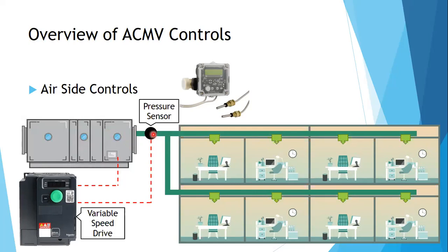So if this pressure sensor, for example, we put a set point of 10 Pascal, and this unit is running at 100%, this pressure sensor will read 10 Pascal. If one room closes, turns off his unit, turns off the supply, and is still giving 80 cmh, the pressure here will go up. The system now will recognize, oh, the pressure goes up from 10, maybe now becomes 12. I need to tell this variable speed drive to slow down. Hey, slow down. This variable speed drive will be connected to your fan motor. So this fan motor speed will lower down. Thereby, the fan will also lower down, and thereby the volume of air will also be lowered down.